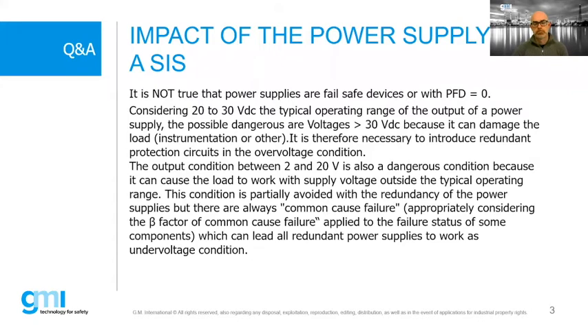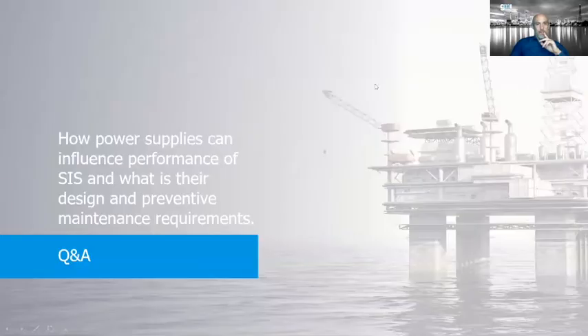But when you are using two power supplies, very important, consider there is a beta factor. The beta factor is the condition that is influencing the system. The beta factor means that the two devices working in a redundant system can fail at the same time with high probability. So the beta factor is very, very important when you use two redundant devices. Okay, the next one is how power supplies can influence the performance of the SIS, and what are their design and preventive maintenance requirements.